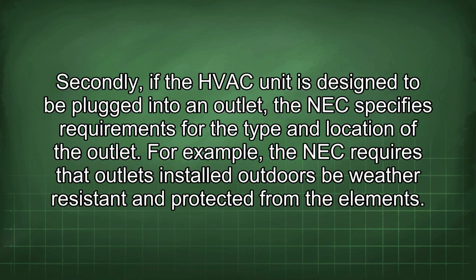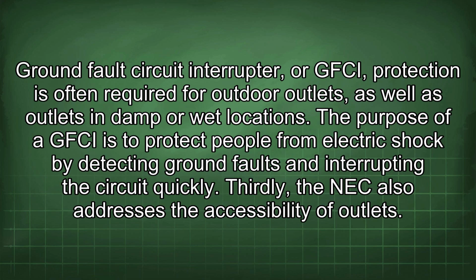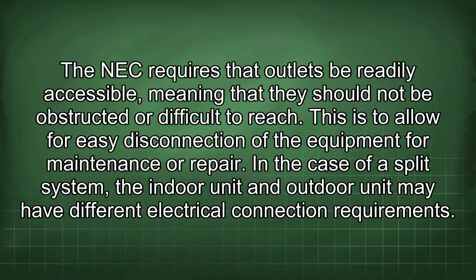Secondly, if the HVAC unit is designed to be plugged into an outlet, the NEC specifies requirements for the type and location of the outlet. For example, the NEC requires that outlets installed outdoors be weather-resistant and protected from the elements. Ground fault circuit interrupter, or GFCI, protection is often required for outdoor outlets, as well as outlets in damp or wet locations. The purpose of a GFCI is to protect people from electric shock by detecting ground faults and interrupting the circuit quickly. Thirdly, the NEC also addresses the accessibility of outlets. The NEC requires that outlets be readily accessible, meaning that they should not be obstructed or difficult to reach. This is to allow for easy disconnection of the equipment for maintenance or repair.